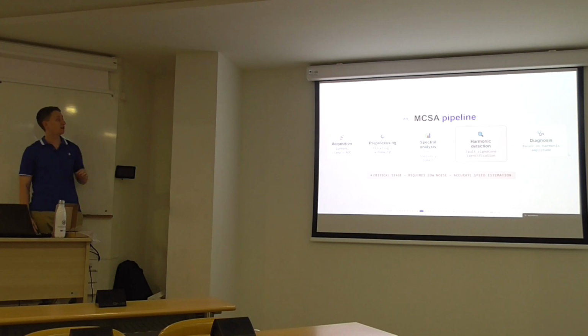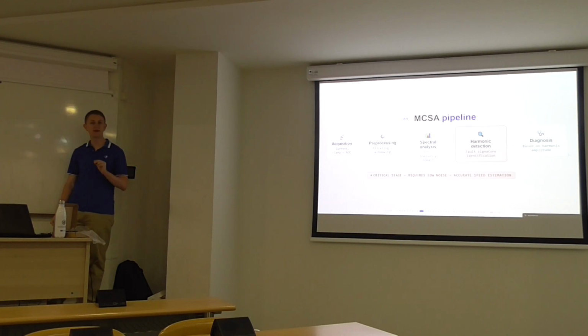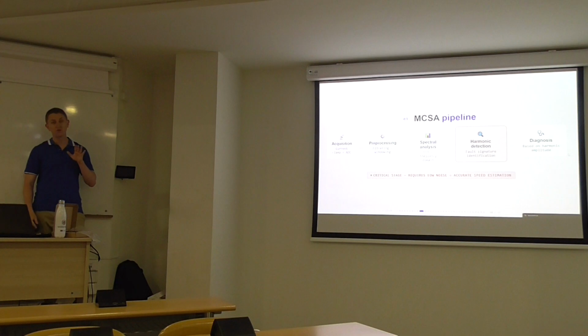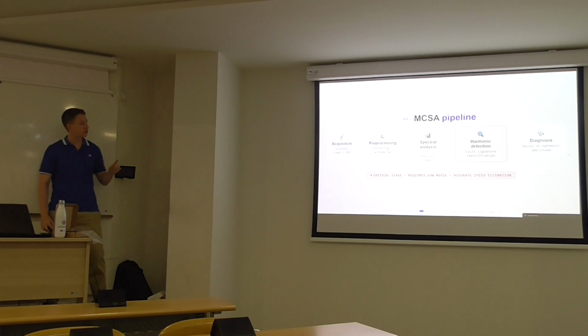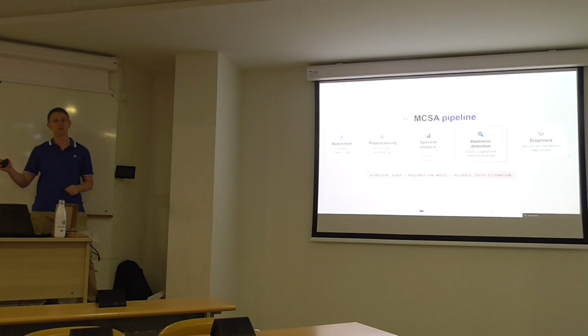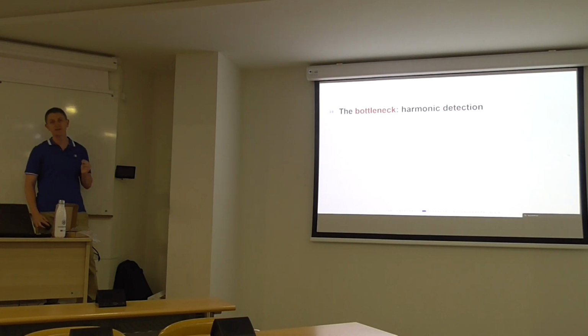So the harmonic detection is a critical stage. It requires low noise and accurate speed estimation. Don't get me wrong here. Diagnosis is equally or even more important than the detection. But if you don't have a reliable detection, you will never be able to provide a reliable diagnosis. So for me, this is the bottleneck of the process, the harmonic detection.